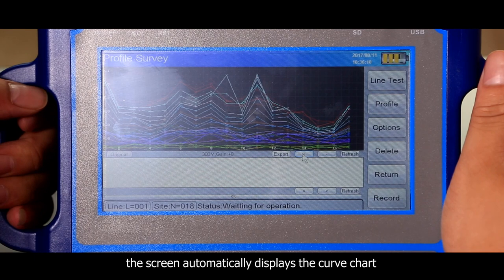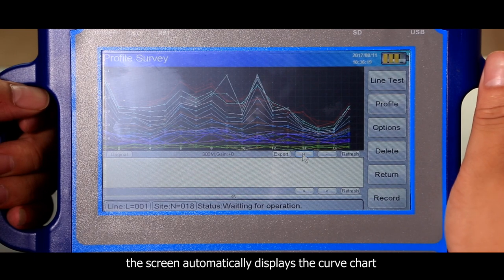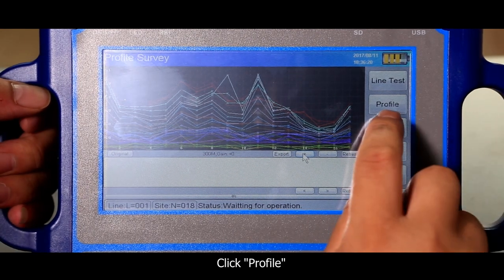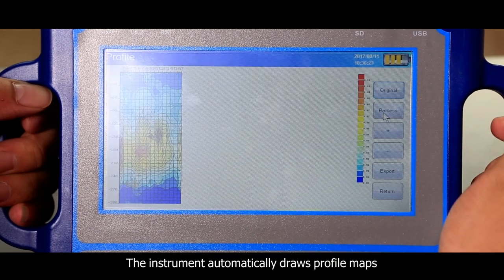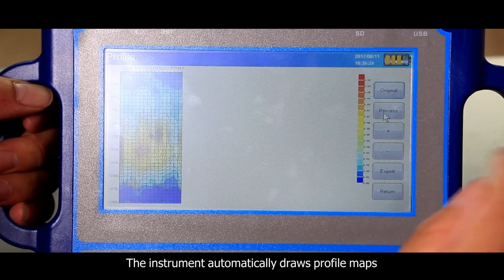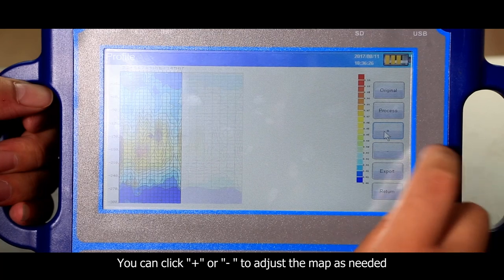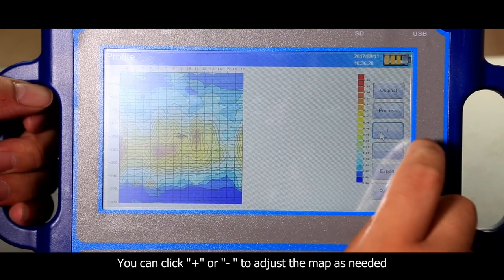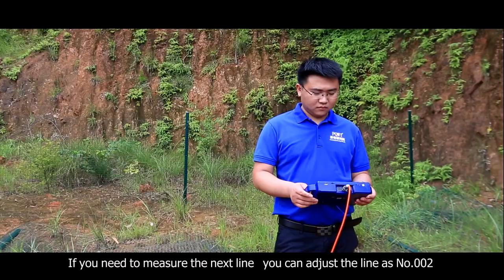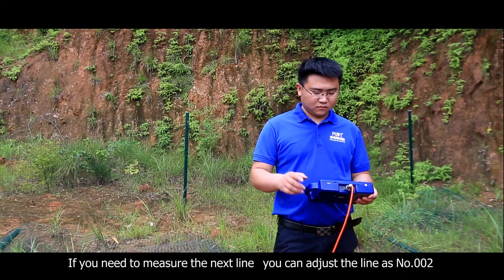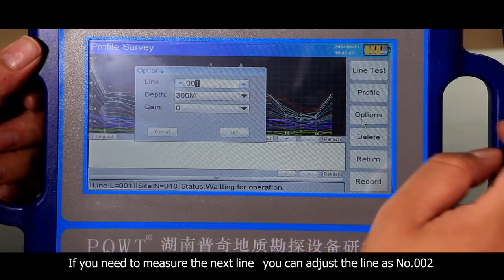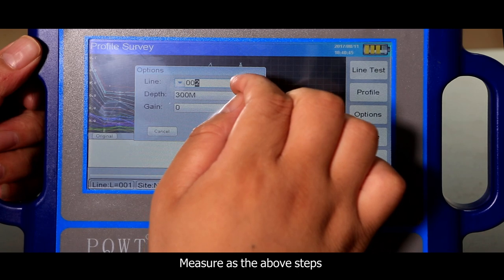When a line measurement is finished, the screen automatically displays the curve chart. Click Profile. The instrument automatically draws profile maps. You can click plus or minus to adjust the map as needed. If you need to measure the next line, you can adjust the line as number 2, measure as the above steps.